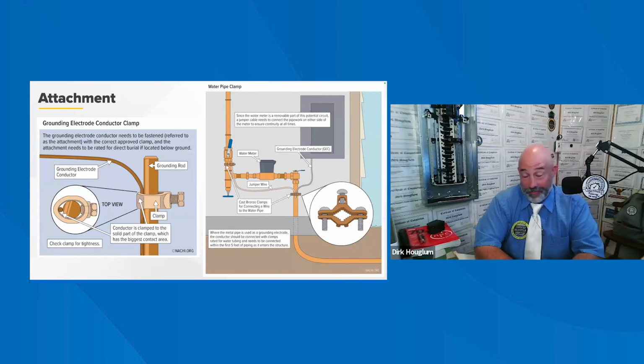The ground wire. The grounding electrode conductor needs to be fastened, referred to as the attachment, with the correct approved clamp. And the attachment needs to be rated for direct burial if located below ground. It is common to see these acorn clamps installed improperly, with the conductor clamped under the screw rather than in the solid part of the clamp, which has the biggest contact area. Can't believe people actually do that.